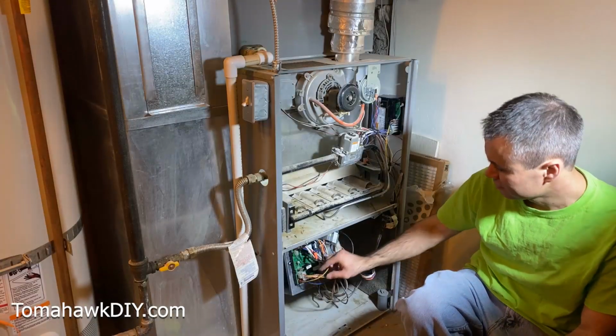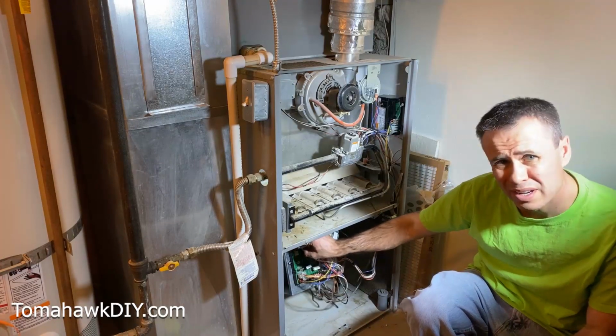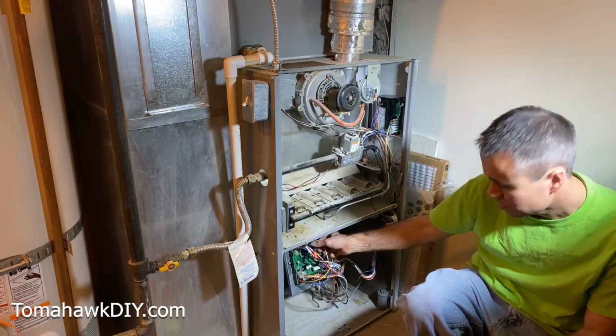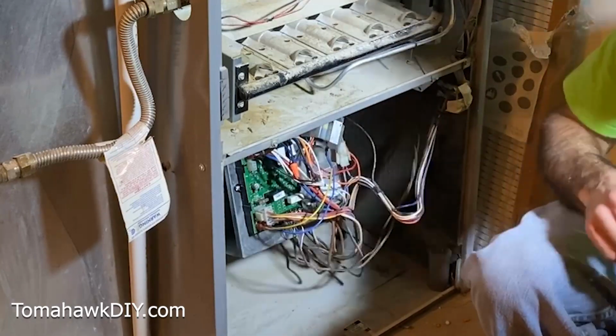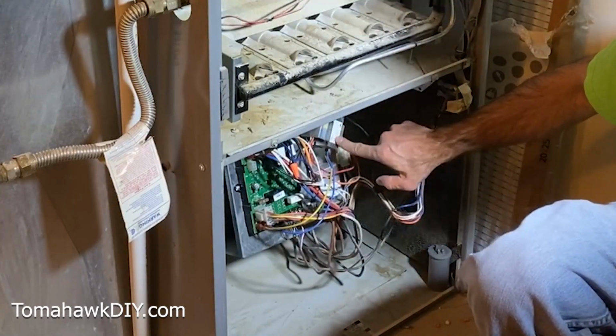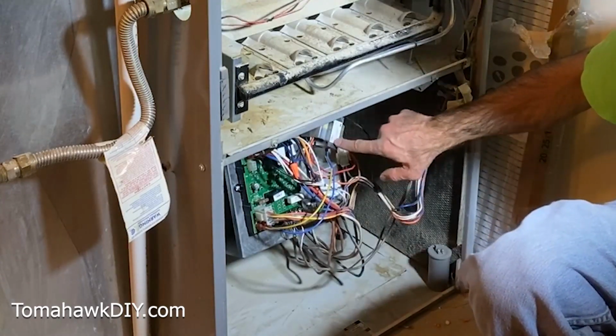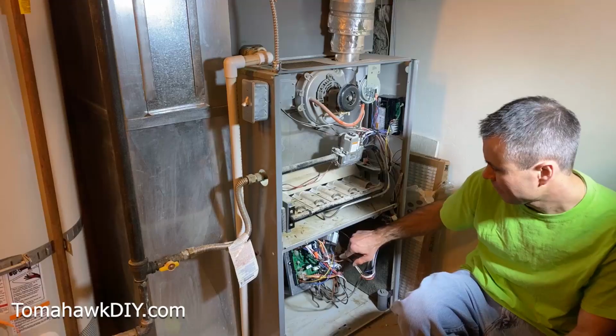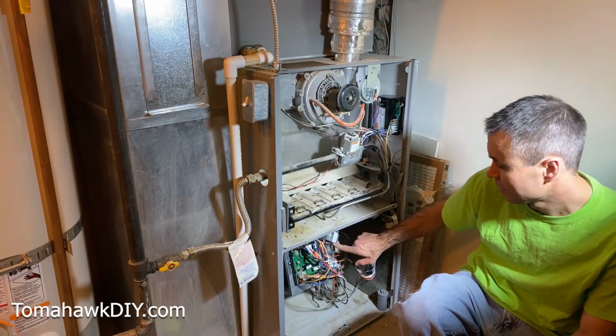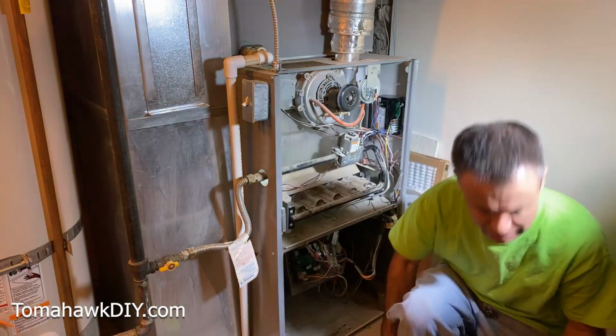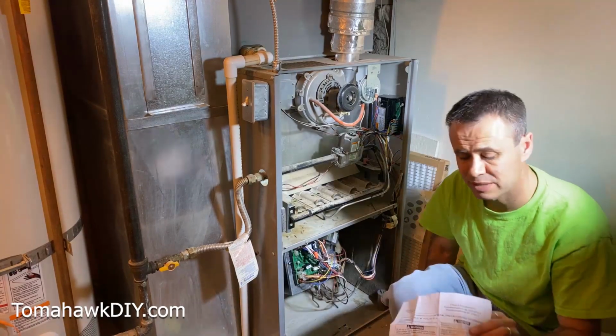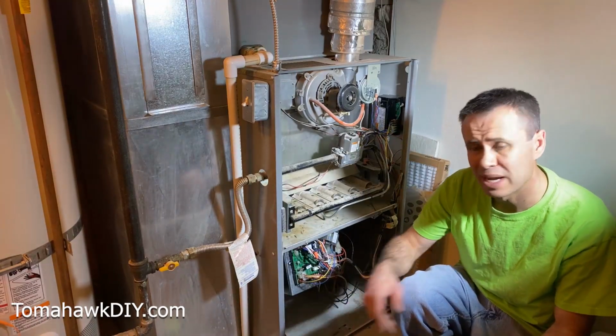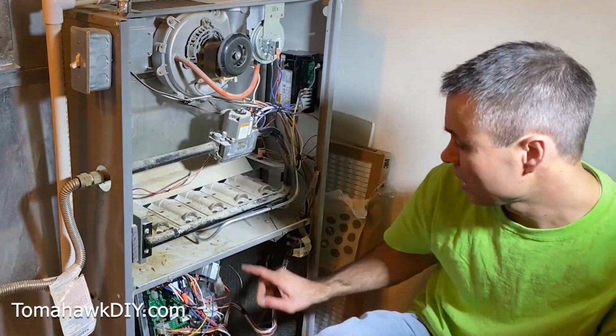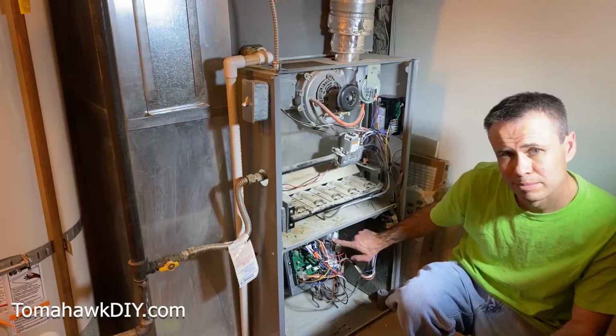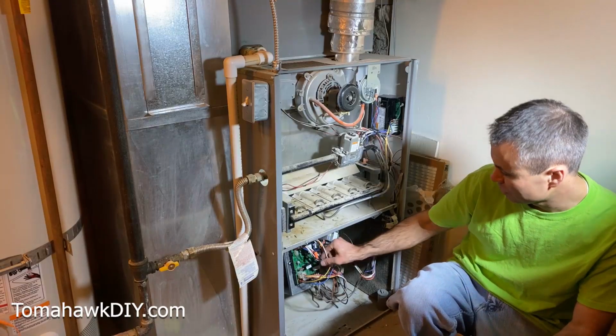I've just finished checking all the wires to make sure they're fully connected. I did find one surprising thing: my transformer is labeled that white is 120 volts and black is the neutral. That was a little surprising. I checked the paperwork that came with the transformer and it said the same thing, black being neutral and white being the 120 volt line. Both places were kind of backwards of what I expected.